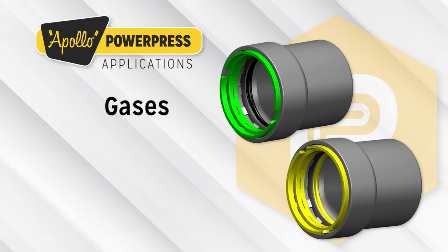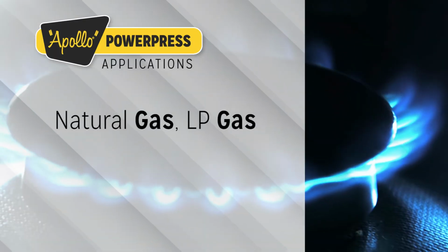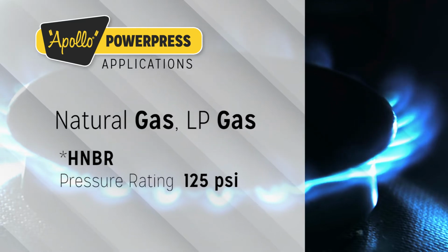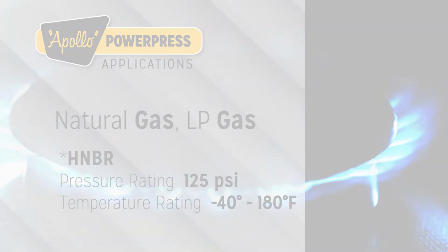Gases are approved with both EPDM and HNBR sealing elements, except where noted. Natural gas and LP gas are approved with HNBR and have a 125 psi max. Temperature range is from -40 degrees to 180 degrees Fahrenheit.